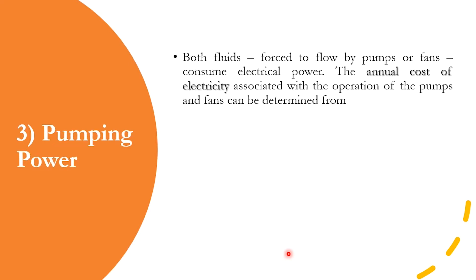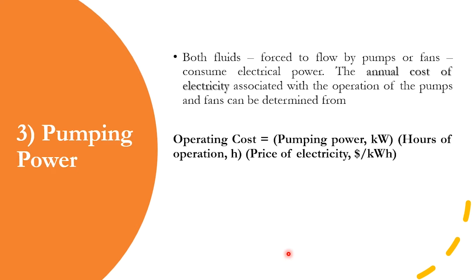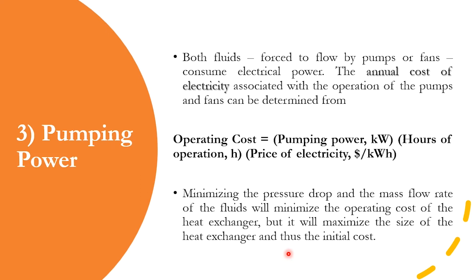The third criterion is pumping power. Both fluids — whether on the shell or tube side — always have to be sent through equipment such as a pump, compressor, or both when gas and liquid are involved. Operating cost is calculated as: pumping power (kW) × operational hours (h) × price of electricity ($/kWh), which gives the total annual operational cost.